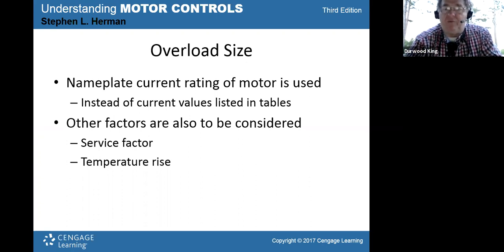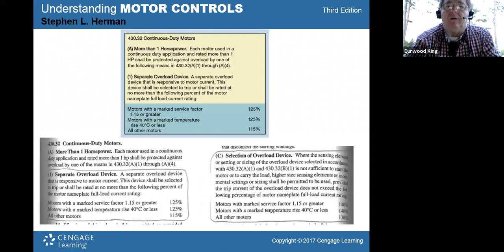So the numbers that I just said, they come from right here. If you look right here, this comes right out of the code book. It says that if it's more than 1 horsepower, you have to have a separate overload device. And for most motors, it's going to be 125% of your full load amps. If it's motors that don't meet this criteria, then it's going to be 115% that you set the overload to whenever you dial it in.